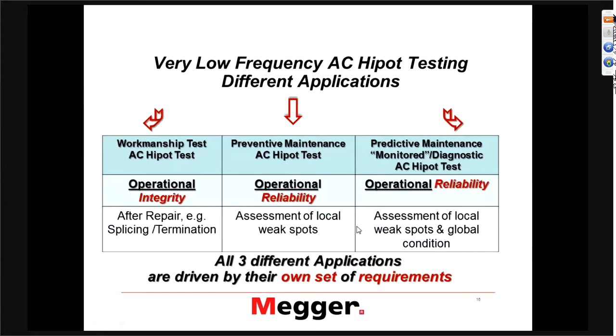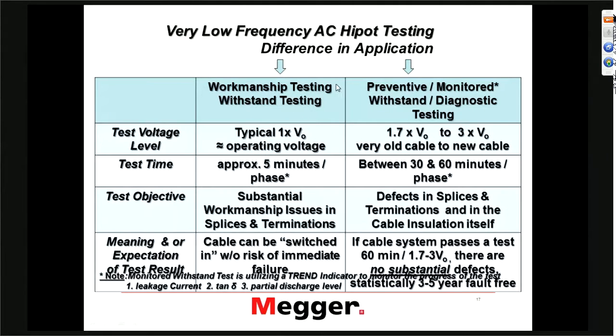All three different applications are driven by their own sets of requirements — test time and test voltage. The workmanship test: many companies use basically operating voltage for maybe five minutes. The test objective is finding substantial workmanship issues in splices and terminations, meaning: we can be switched in without risk of immediate failure. The preventive or monitored withstand test uses a minimum voltage of 1.7 U-naught — that comes from the fact that in a three-phase system, if one phase goes to fault you might have system voltage between the other two phases. The test time is between 30 and 60 minutes per phase.